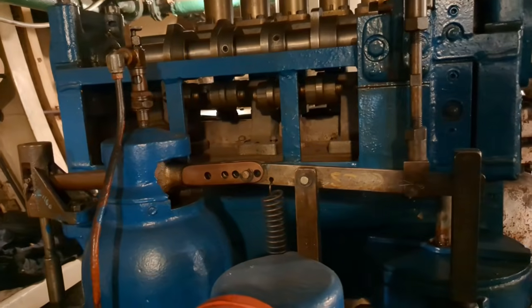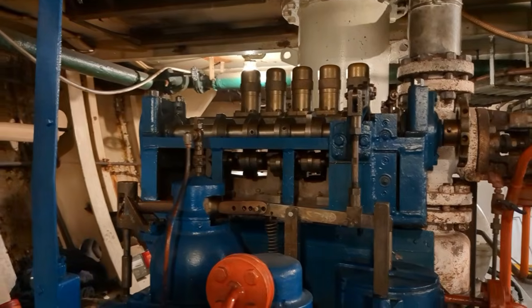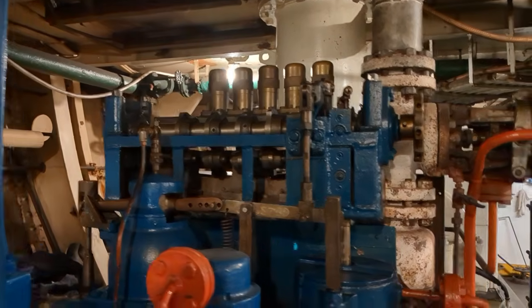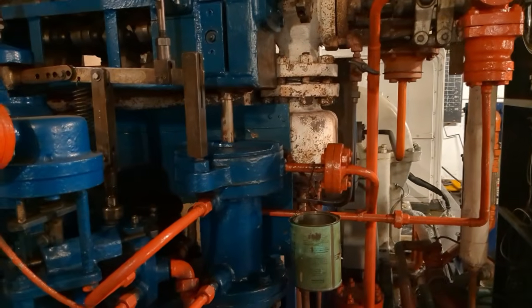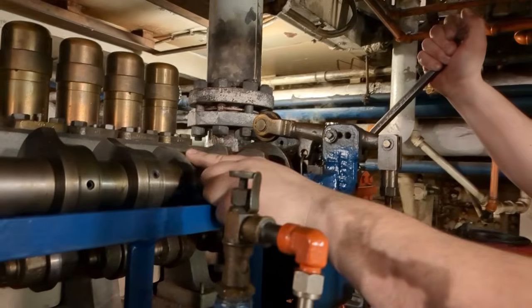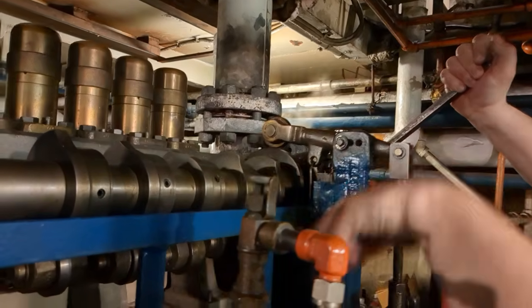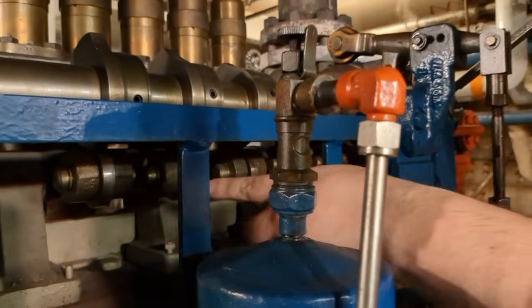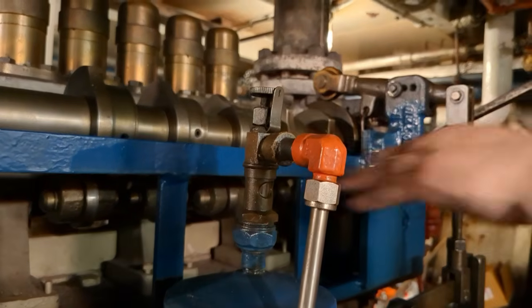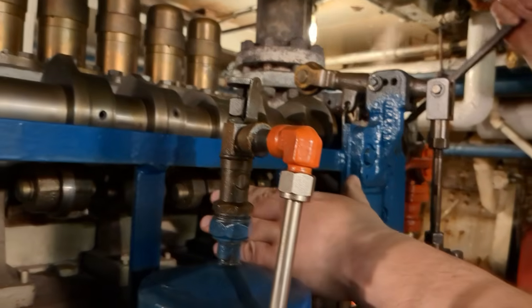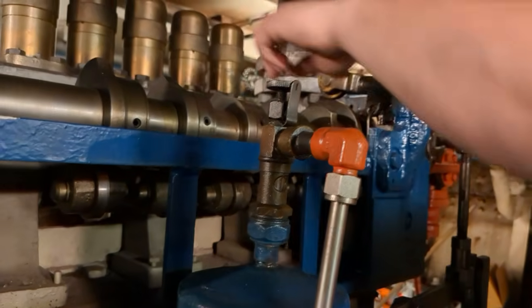The pilot valve directs high pressure oil to a hydraulic piston, which rotates a series of cams that open or close the steam nozzle valves. Rather than throttling the steam, the governor opens the nozzle valves one at a time, keeping the steam pressure close to boiler pressure and improving efficiency.